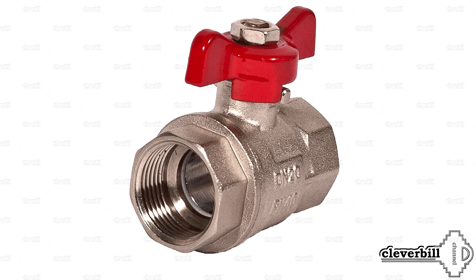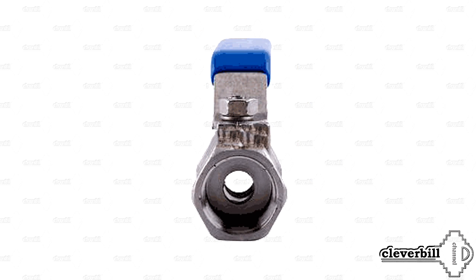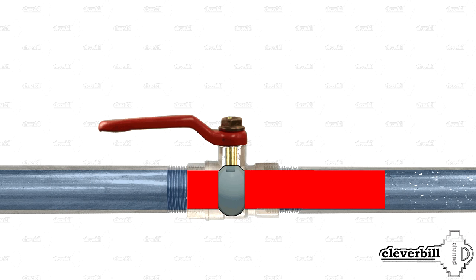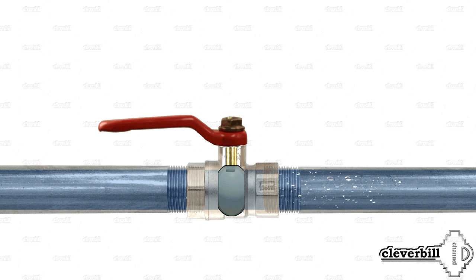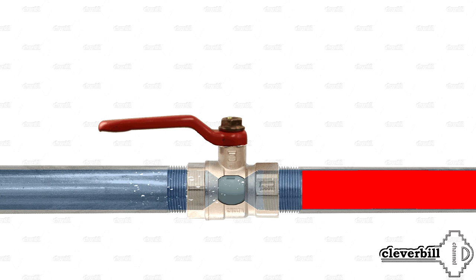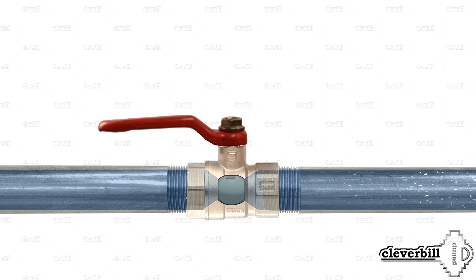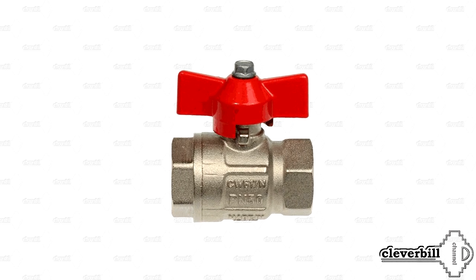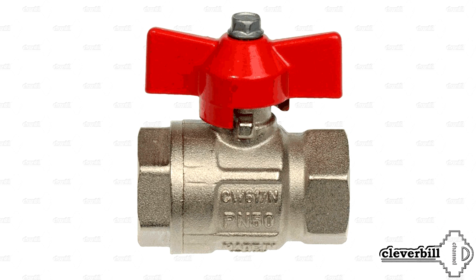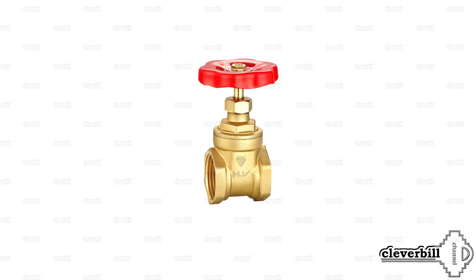Ball valves can be full-pass or reduced. A full-pass valve has a passageway in the ball equal to the inner diameter of the connected water pipe, which excludes hydraulic resistance in that section. A reduced valve has a smaller hole in the ball relative to the inner diameter of the connected pipe. Such valves are used where an increase in hydraulic resistance is not particularly critical. Ball valves are used everywhere in water supply, heating, and even gas supply — and in household water supply, the ball valve has pushed aside its older brothers, the gate valve and the stop valve.